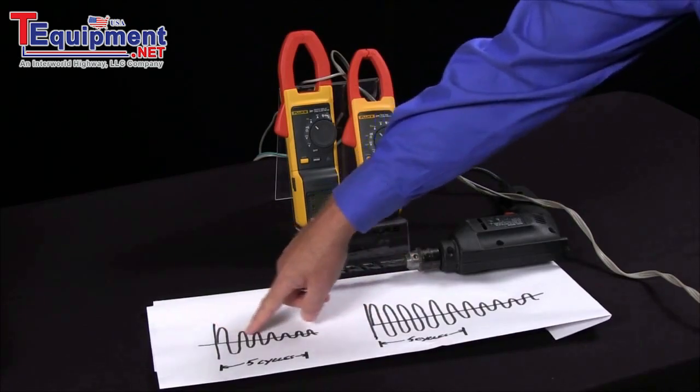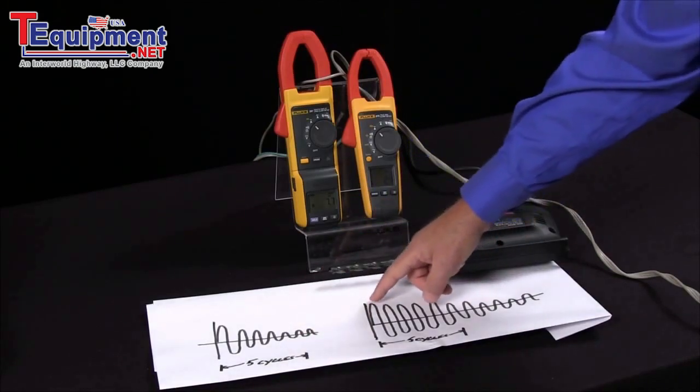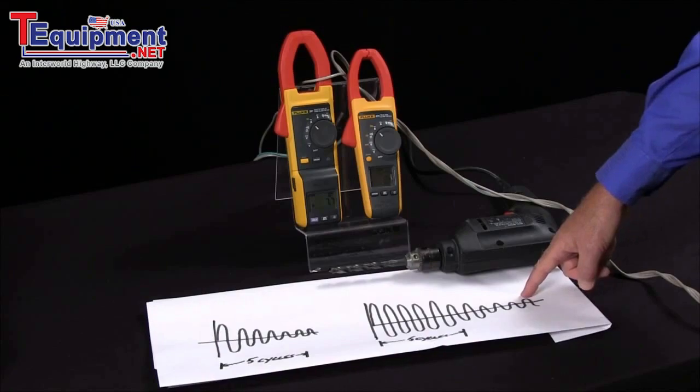With a good inrush current it settles out very quickly with a good motor. If we have a bad aging device, it may take it quite a long time to settle out.